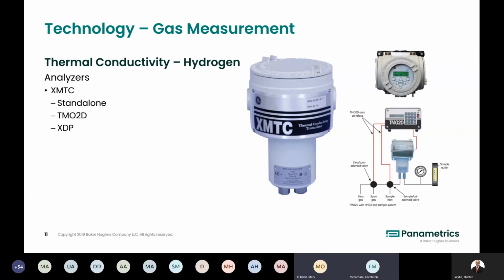So the electrical side of things is usually pretty obvious. If your display is not working, you can check the output from the transmitter. Do you still have a 4-20, and is that 4-20 being displayed on your transmitter? Again, there are troubleshooting instructions in the manuals for each of the analyzers, and they cover 90+% of the issues that you may encounter over the long lifetime of these transmitters.